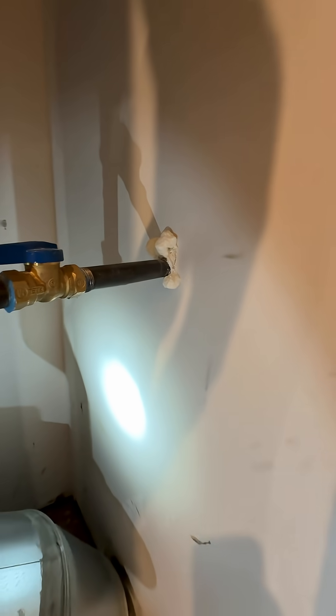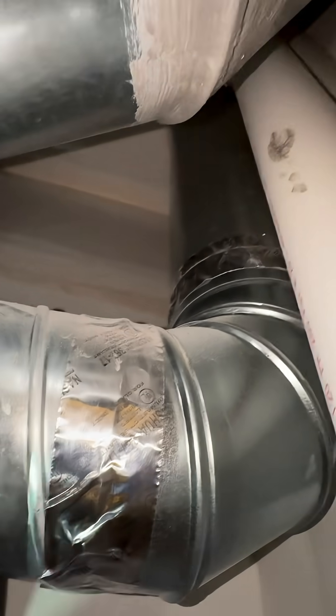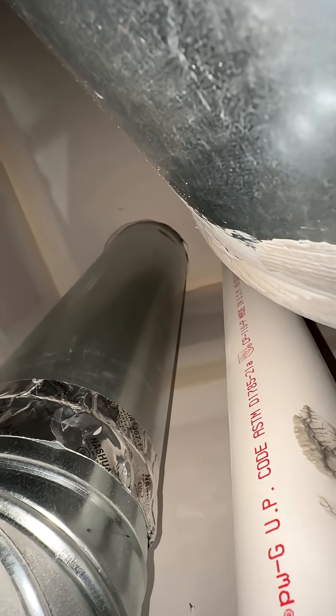Fire-rated products are usually tinted red for easy identification. I find this in almost every new build I inspect, and I'm always curious why code inspectors miss it on every single house. If you just bought a place, it's worth checking out, because half-done fire protection isn't fire protection at all. Thanks for watching, and have yourself a great day.